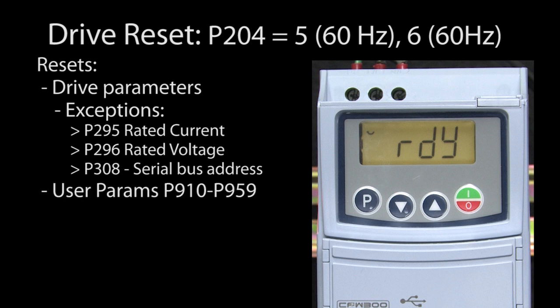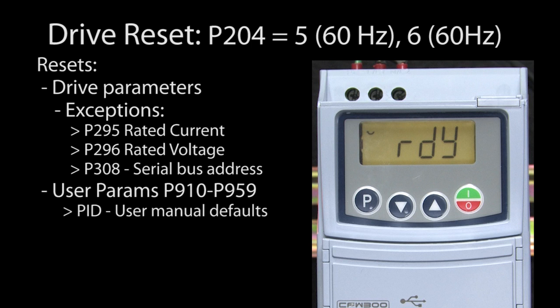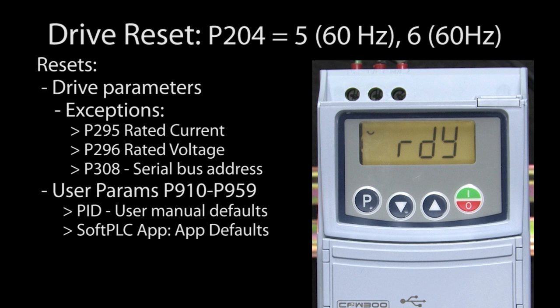It also resets the user parameters 910 through 959. If you were using the built-in PID app, they get reset to the defaults shown in the user manual. If you were using a custom soft PLC app, they get reset to whatever your soft PLC app had assigned as the default values.